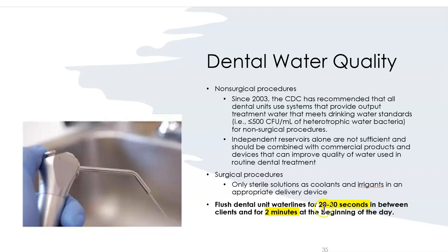Water lines must be flushed: 20 to 30 seconds between clients, and two full minutes at the beginning of each day. Timing matters — set a timer. If we don't flush, biofilms and bacteria build up inside the lines. Also, never let a client close on the suction to create a vacuum seal — this can cause backflow, pushing contaminated material back out of the suction.